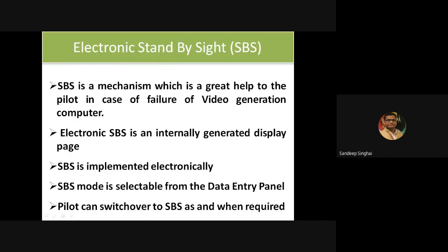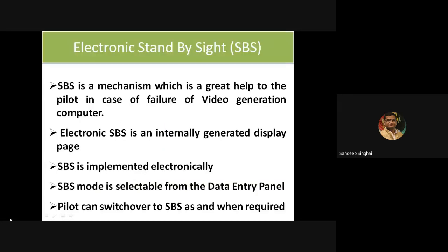The other thing which I have done personally is the electronic standby sight. It is a mechanism which is a great help to the pilot in case of failure of the video generation computer. Electronic SBS is an internally generated display page. It is implemented electronically and is selectable from the data entry panel, as well as in case when the automated switch off of MC signals is detected by the BIT system.